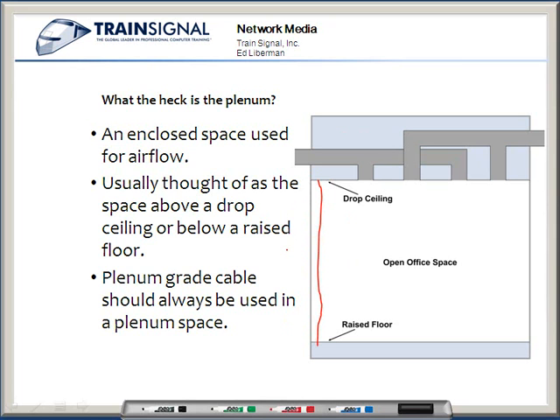Now, another way you can avoid this - because plenum is more expensive, and yes it is - the way you can avoid using plenum grade cable and still stay within fire code is to run your cables through some form of conduit, a pipe, to make sure you are safe.